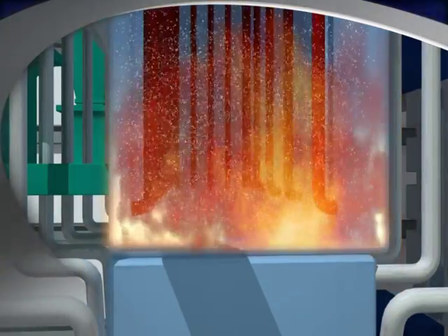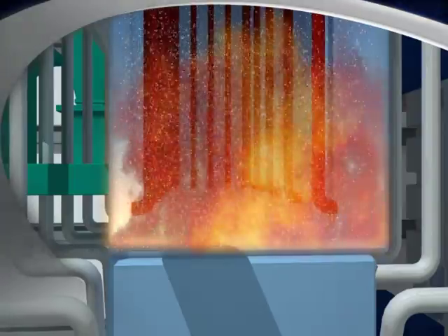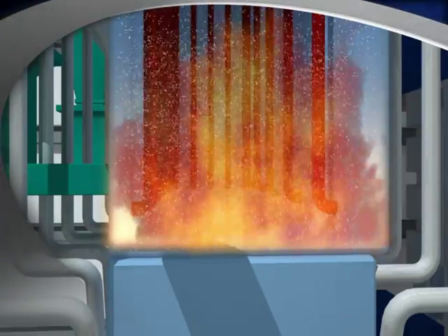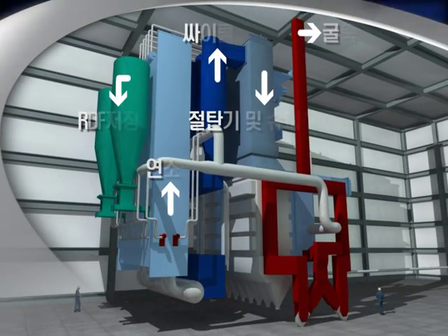The produced RDF is moved to the storage silo and is burned in a circulating fluidized boiler, producing hot flue gas of 900 degrees Celsius. The gas exchanges its heat with the evaporator, superheater, economizer, and air heater in series.